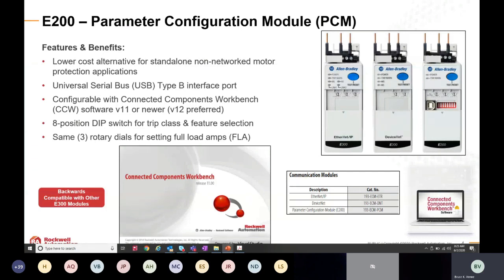One nice thing about the E200 is that it's configurable with one of Rockwell's free software interface packages called Connected Components Workbench, or CCW. The E200 works with software version 11 or newer, and works a bit nicer in version 12 if you're familiar with that layout. CCW is a free utility somewhat similar to Studio 5000, but not quite as costly, providing a much more elegant interface for configuration and monitoring of the device. Keep in mind that the E200 supports that feature.